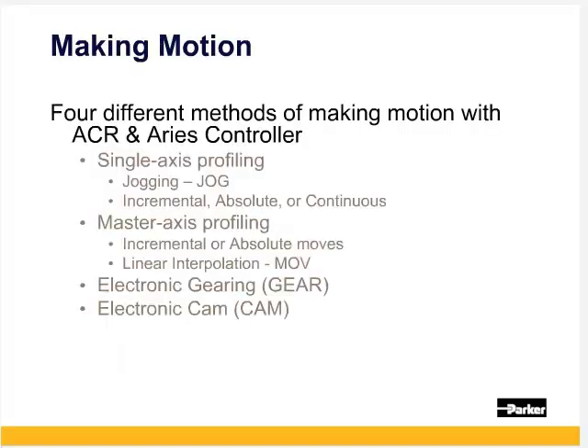The ACR and Aries controller allows four different types of motion. Single axis moves are done with the JOG. These can be incremental or absolute distance commands or continuous velocity moves. Interpolated or coordinated moves use the master axis profiling and allow multi-axis moves. Gearing and camming can also be programmed, but will be covered in the advanced motion training.